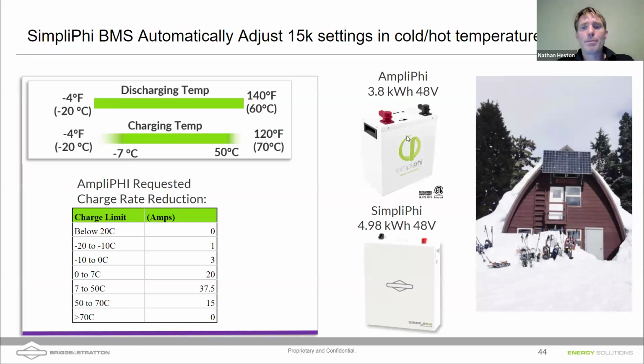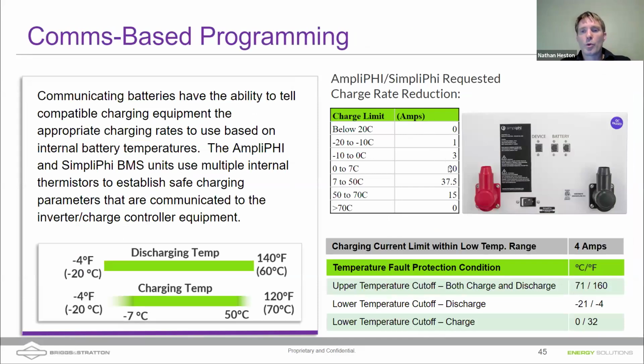Earlier, it was asked about temperatures and cold environments. And one of the nice things about our communicating batteries and our fairly sophisticated BMS inside our batteries is the fact that these batteries automatically control their charge rates in extreme temperatures, which allows us to have a much broader charging and discharging range than most of our competitors. We can actually charge slowly at low temperatures. That warms up the batteries due to the high levels of internal resistance in the electrolyte at those temperatures. That heats up the batteries, and then we can increase that charge rate. So as our batteries get warmer and warmer, we increase our charge rate until we get into that optimal window from about 7 Celsius to 50 degrees Celsius.